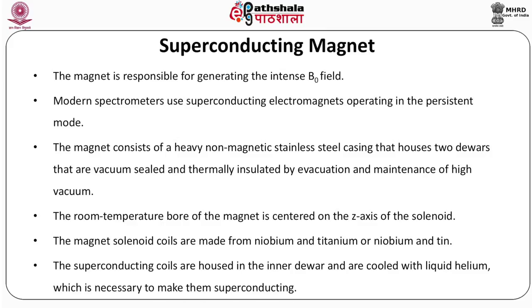The magnet is responsible for generating the intense B0 field. Modern spectrometers use superconducting electromagnets operating in the persistent mode. The magnet consists of a heavy non-magnetic stainless steel casing that houses two Dewars that are vacuum sealed and thermally insulated by evacuation and maintenance of high vacuum. The room temperature bore of the magnet is centered on the Z axis of the solenoid coils. The magnet solenoid coils are made from niobium and titanium or niobium and tin. The superconducting coils are housed in the inner dewar and are cooled with liquid helium, which is necessary to make them superconducting.